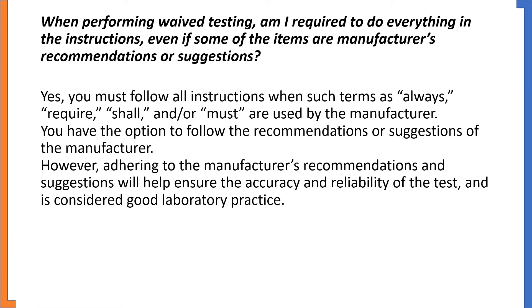When performing waived testing, am I required to do everything in the instructions even if some of the items are the manufacturer's recommendations or suggestions? Yes, you must follow all instructions when such terms as 'always,' 'require,' 'shall,' and/or 'must' are used by the manufacturer. You have the option to follow the recommendations or suggestions; however, adhering to them will help ensure the accuracy and reliability of the test and is considered good laboratory practice.